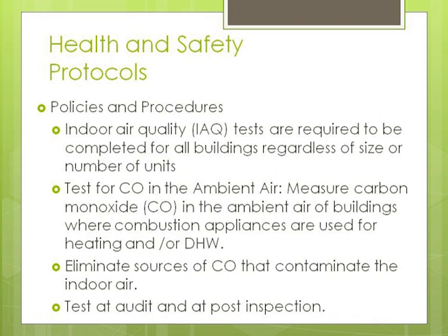While we were there, we also had to give them some basic safety information. We would test the carbon monoxide levels in a couple of different areas of the home. We'd also test the carbon monoxide levels at the gas oven — we'd turn the oven on, leave it on for a few minutes, and then test the air around there to see if it had too much carbon monoxide.